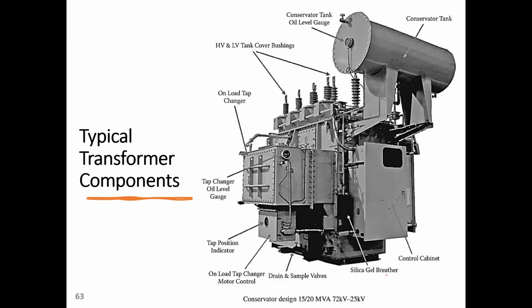We have also what's called silica gel breathers, guys. The silica gel is an indicator of the moisture inside the transformer oil. The silica gel has two colors, and the color will change according to the moisture inside the transformer. So the silica gel breather and indicator refers to any kind of moisture inside the transformer oil, in order to consider replacing it or doing some maintenance. We have the control cabinet. The control cabinet is controlling the whole transformer, controlling the connections, and controlling the voltage levels if you would like to change something or do anything here.